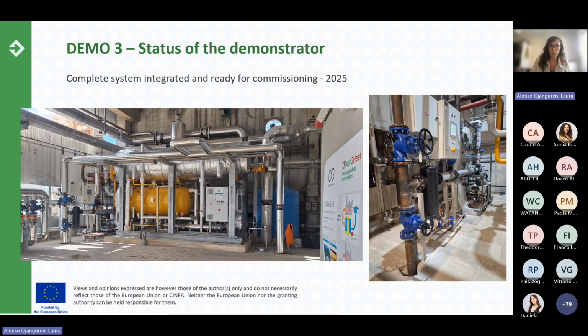And as you can see, we have two valves. The valve on the top allows the steam to be rejected to the atmosphere, because the first tests were done rejecting the produced steam to the atmosphere. And then when it was sure that everything was working fine, we used the other valve to conduct the produced steam to the medium pressure steam header in the plant.